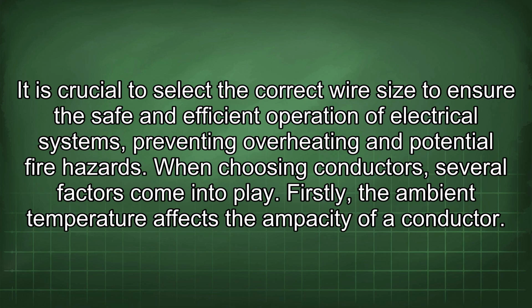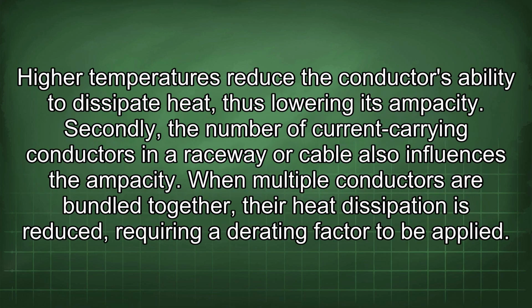When choosing conductors, several factors come into play. Firstly, the ambient temperature affects the ampacity of a conductor. High temperatures reduce the conductor's ability to dissipate heat, thus lowering its ampacity. Secondly, the number of current-carrying conductors in a raceway or cable also influences the ampacity. When multiple conductors are bundled together, their heat dissipation is reduced, requiring a derating factor to be applied.